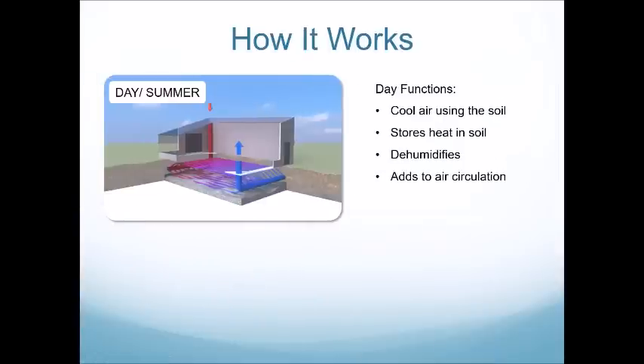Our GAHT systems work both in daytime and nighttime. The typical GAHT action during the daytime, or in the summer, involves the red inlet pipe at the north side of the greenhouse, positioned high so that it can pull hot air down underground into the main manifold. Air is then transferred across a smaller diameter pipe to the return manifold, where it's cooled using the soil and that heat is stored. This action of cooling the hot air also dehumidifies the air that comes out cooler and less humid, and adds to circulation within the greenhouse.